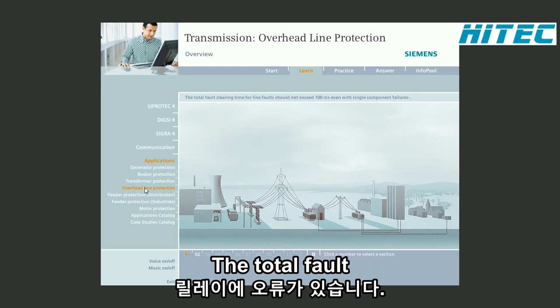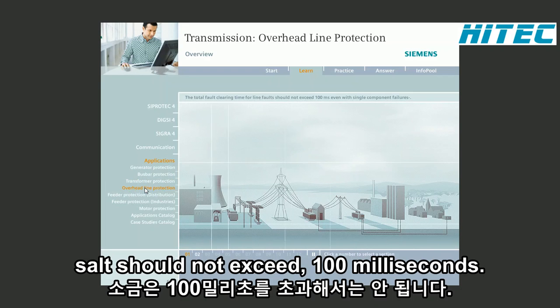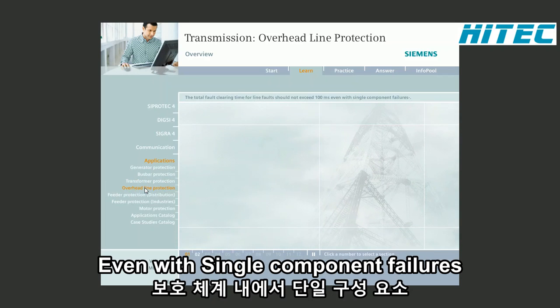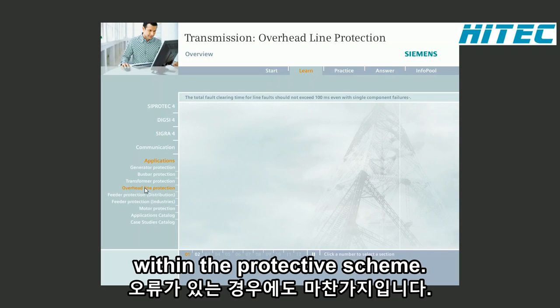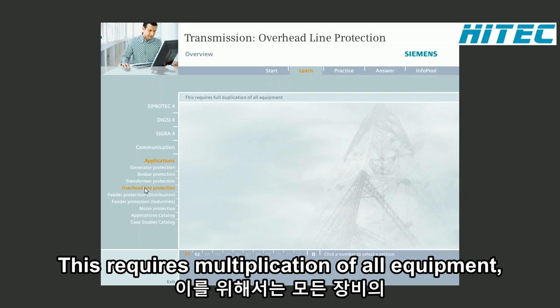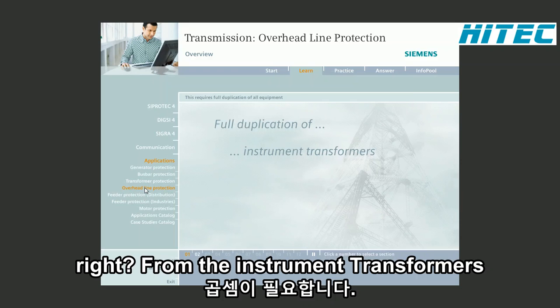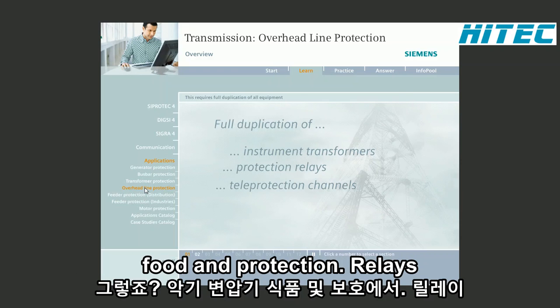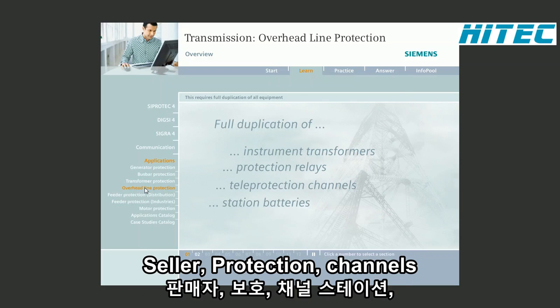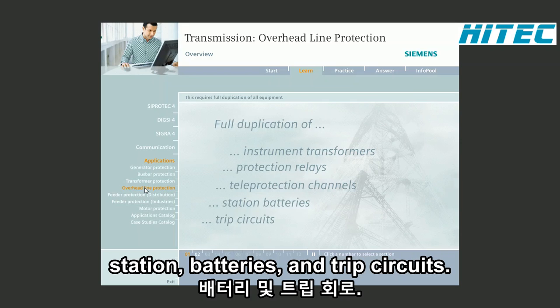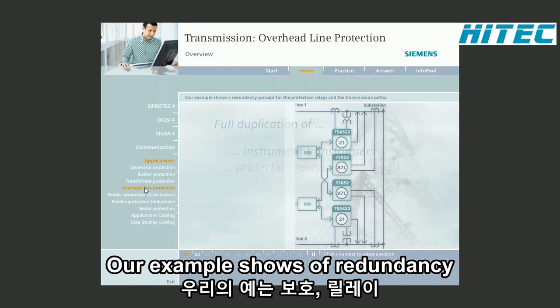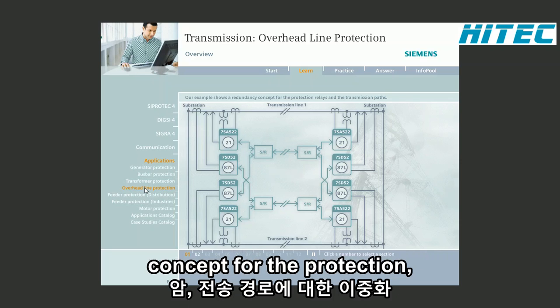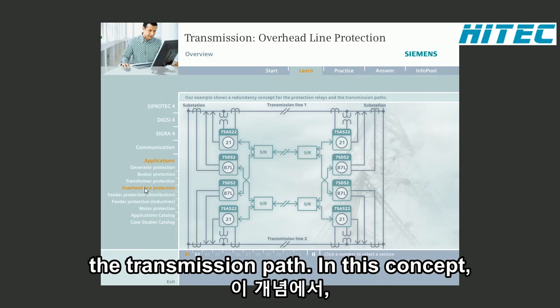The total fault clearing time for line faults should not exceed 100 milliseconds even with single component failures within the protective scheme. This requires full duplication of all equipment right from the instrument transformers through the protection relays, teleprotection channels, station batteries, and trip circuits. Our example shows a redundancy concept for the protection relays and the transmission paths.